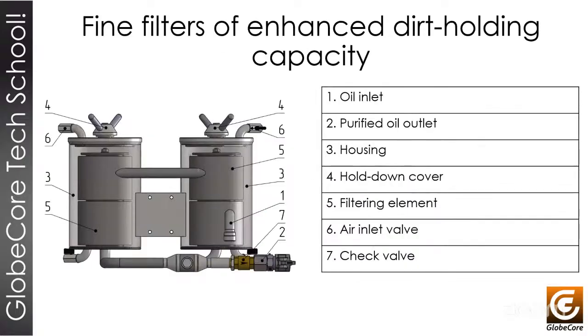Another really important piece of equipment for us is the fine filters in the machine. Usually we have 2 or 4 filters inside the housings. These filters will remove the fine particles of solid contamination, small particles. They are really simple to replace. You will release this nut here at the top, and when you release that, you will have access to remove the different filter elements and reduce the contamination inside the oil.